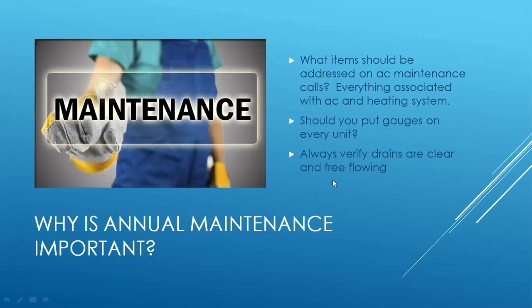And this is a big one for me. Always verify drains are clear and free flowing. Can't preach that enough. I was sued once because of a drain. Turns out that I did my portion of the drain, and because I had like 7 years of documentation of clearing drains for them and everything was detailed, it went in my favor. It wasn't my fault, but had I not had all the documentation, and done things every time the same way, it could have gone the other way for me.